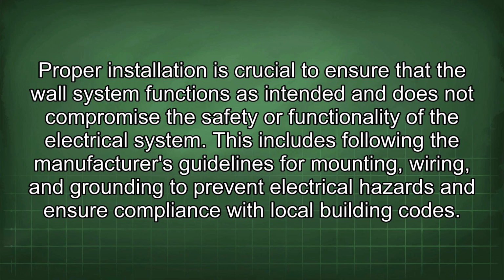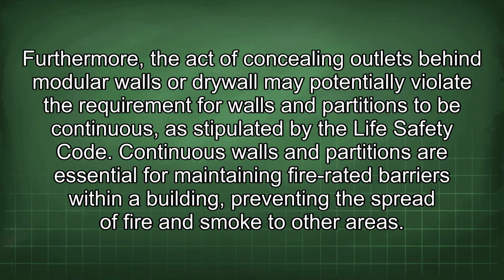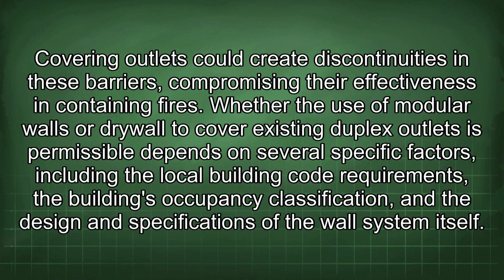Furthermore, the act of concealing outlets behind modular walls or drywall may potentially violate the requirement for walls and partitions to be continuous, as stipulated by the Life Safety Code. Continuous walls and partitions are essential for maintaining fire-rated barriers within a building, preventing the spread of fire and smoke to other areas. Covering outlets could create discontinuities in these barriers, compromising their effectiveness in containing fires.